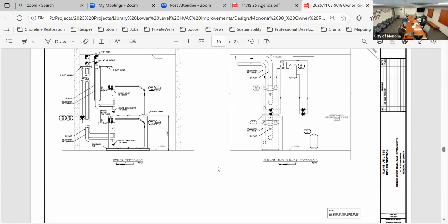We have, and there's other things too. We've gone through heat exchangers on our other boilers because it just eats through the aluminum. Moving forward, when we redo any boiler systems or otherwise, we'll be putting in boiler loop treatment. These are all closed loops, so it's the same water recirculating over and over again. When we do have loss of water, like we get a leak, or sometimes there can be evaporation, not too much, we'll have to push fresh water in, but it'll also push through the treatment.